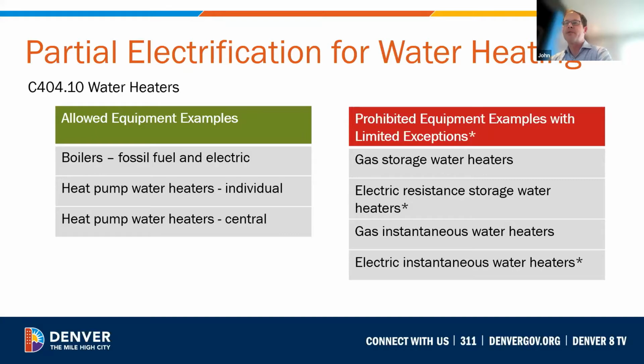Water heating end uses may also be met with electricity-based heating systems. Heat pump water heaters may be used to serve a single load or a central load. Beginning January 1st of 2024, the code prohibits the use of gas storage water heaters and gas instantaneous water heaters, with a few exceptions. Exceptions are allowed for resistance heating elements within the heat pump water heater equipment, and electric resistance elements used in a recirculation loop for temperature maintenance for a central system. Exceptions are also given for electric storage water heaters allowed for tanks smaller than 20 gallons. And indirect hot water storage tanks that have no heating elements, so basically serve as storage, are also allowed by the code.